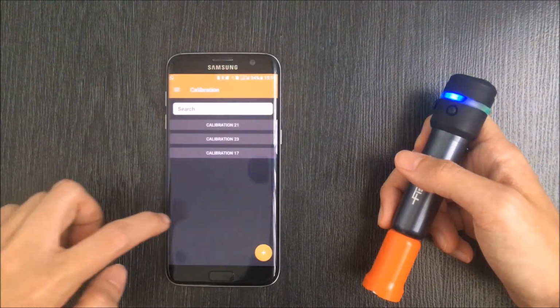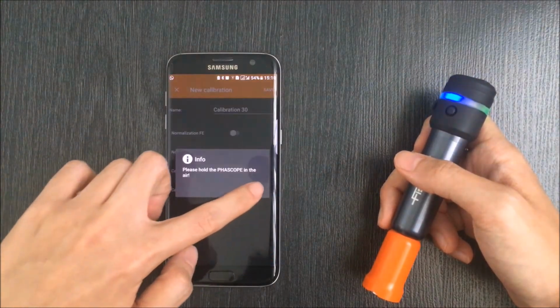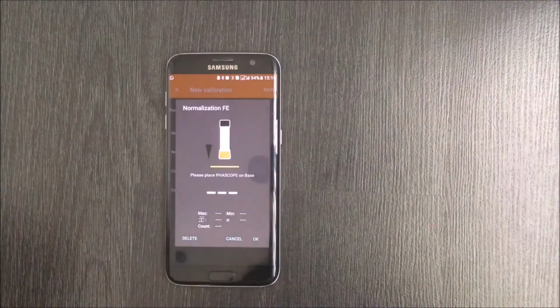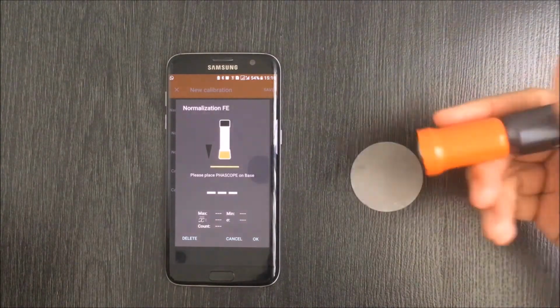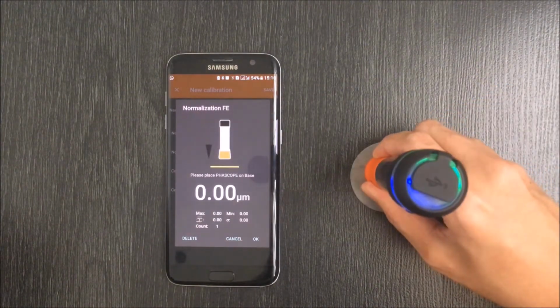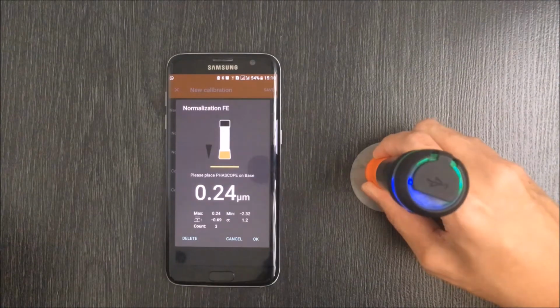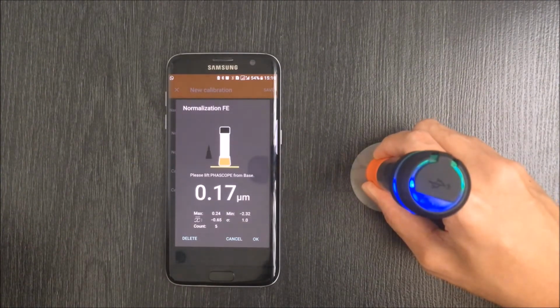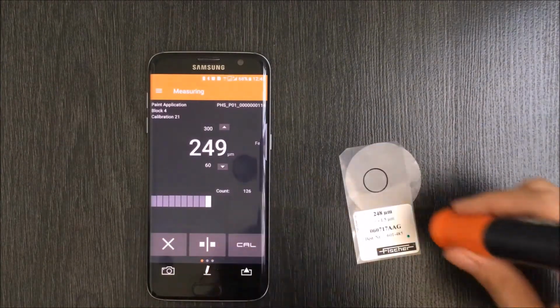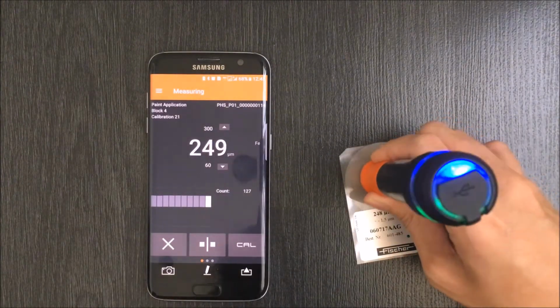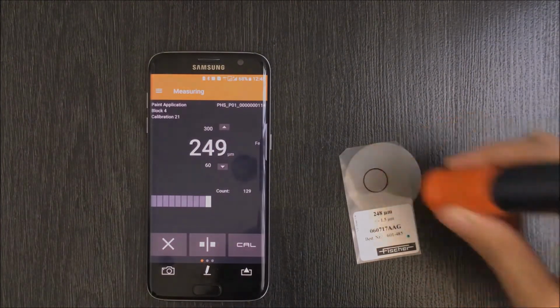Normalization is the simplest type of calibration offered. When you first receive the PHASCOPE paint, perform a normalization on the uncoated surface to check if the measured thickness is accurate. If the value is accurate, then no further calibration is required. If you would like to get a more accurate reading, use the calibration setting.